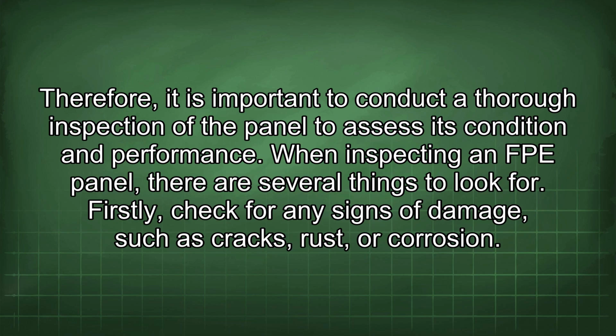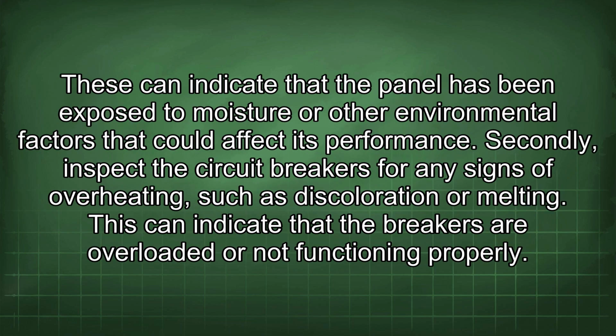When inspecting an FPE panel, there are several things to look for. Firstly, check for any signs of damage, such as cracks, rust, or corrosion. These can indicate that the panel has been exposed to moisture or other environmental factors that could affect its performance. Secondly, inspect the circuit breakers for any signs of overheating, such as discoloration or melting. This can indicate that the breakers are overloaded or not functioning properly.